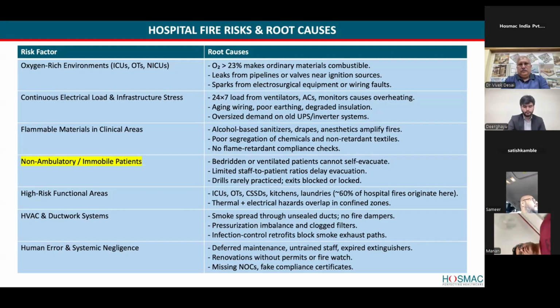There you will have a smoke exhaust fan either mounted outside or on the terrace level, and it will be connected by means of a smoke exhaust duct. So whenever the occupants are passing through a fire escape path, we have a smoke duct in the passages above the false ceiling. So smoke gets sucked from the escape passages and exhausted out to the atmosphere, so that occupants get a clear, smoke-free environment while escaping from the area.